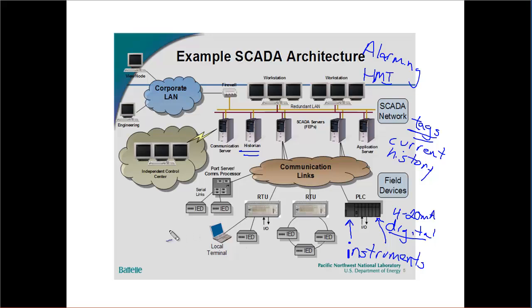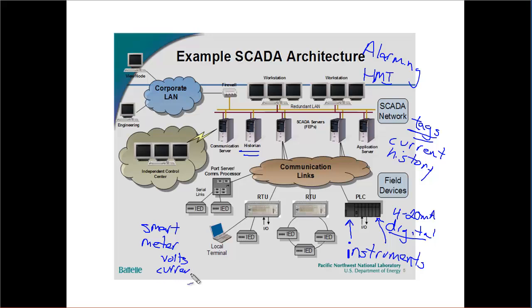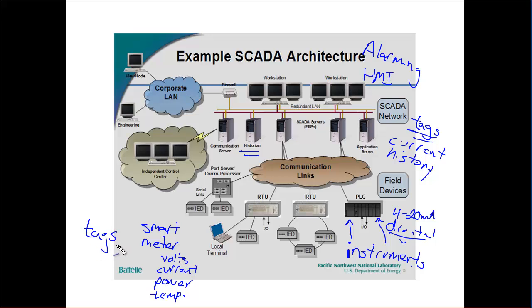Let's say we have a smart meter at somebody's house. It might be measuring volts, current, and power consumption, and it might even be taking a temperature reading — because knowing how hot it is where your customers are helps predict how much electricity they're going to use. So this smart meter is going to have multiple tags inside of it: a tag for volts, a tag for current, a tag for power, and so on. That would be communicated back into an RTU through the communication interface and come back up.